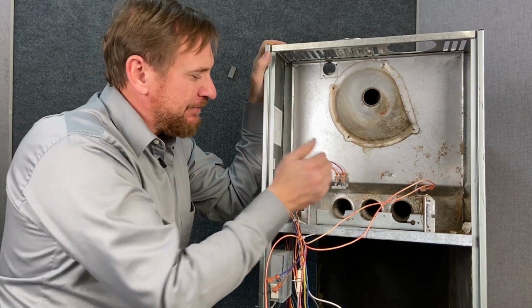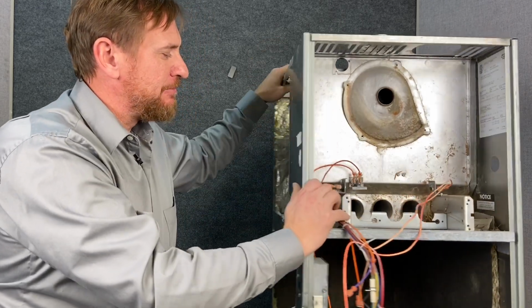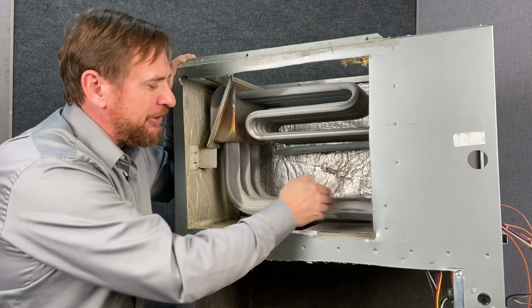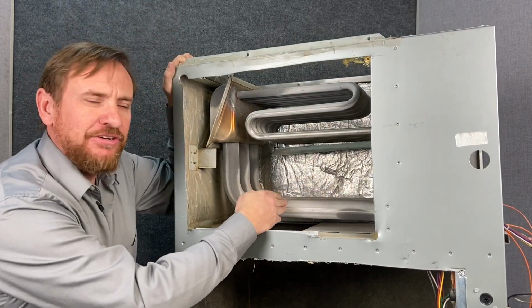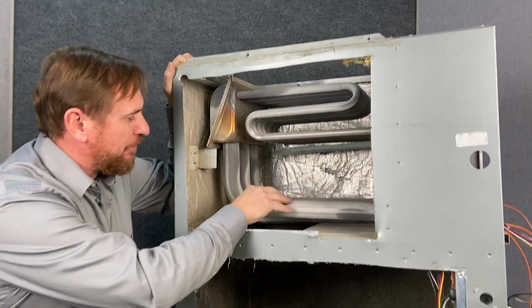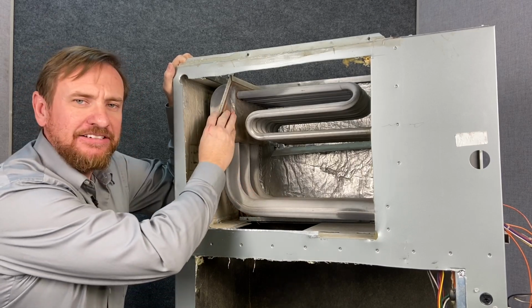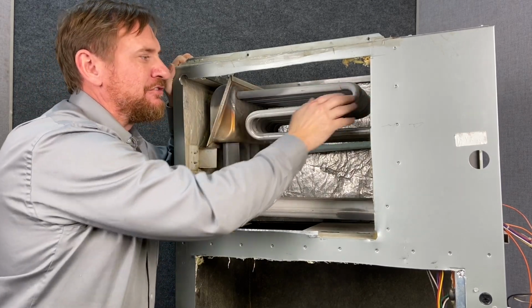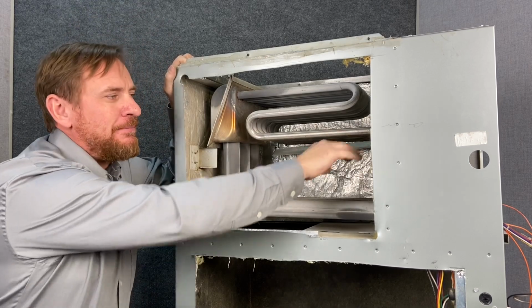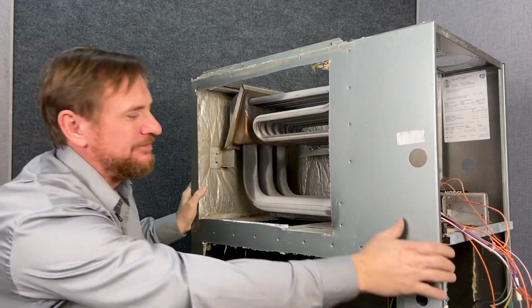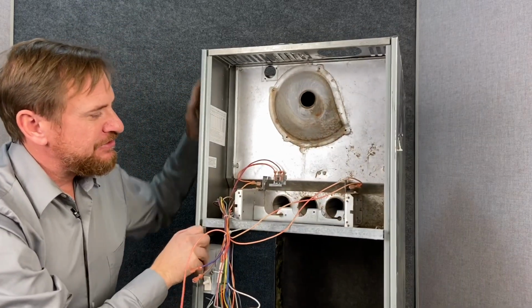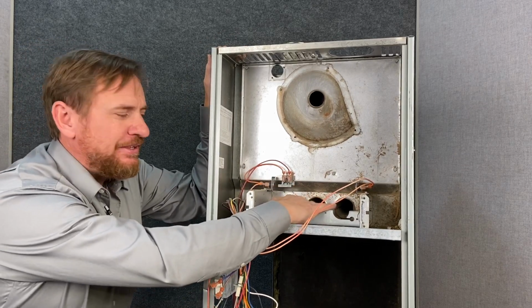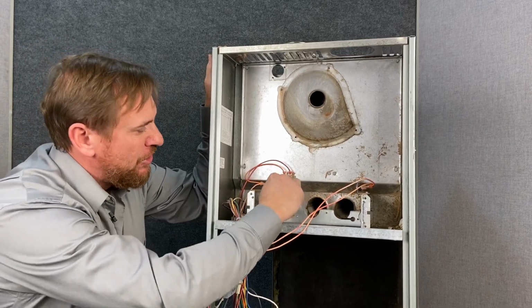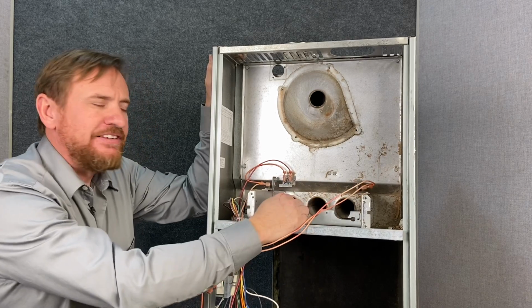So this is where the flame is going to throw inside that heat exchanger, burning in those tubes. And the flame only burns right about in here or so before it burns out. The rest of this is just hot gas. The hot gas collects here. We separate the hot gas through all these smaller tubes back to this collector plate. So now notice, right where the burners are, right where the flame goes into that heat exchanger, we have 1, 2, and 3 sensors here.